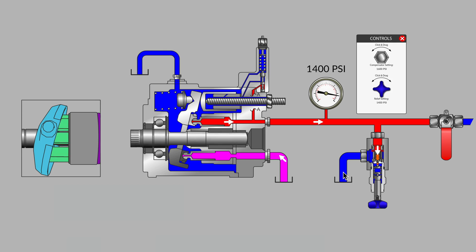Without the help of a cutaway and flow arrows on a normal hydraulic system, we might detect this condition by the sound that the relief valve makes. We would probably also notice, if we measure temperatures, that the hydraulic relief valve will be the hottest component in the system.